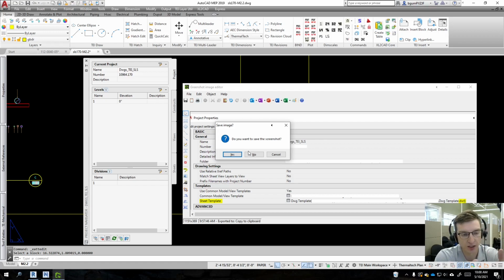So, and then last tidbit, just recall that if you are using Design Master on the electrical side of things, you need a different folder for your Design Master drawings to be located in, and that folder should be named Drawings Electrical, and it should be located at the same directory where your .apj file is. The .apj is the Project Navigator source file. So you'll have Drawings Electrical, and then the .apj in that directory.